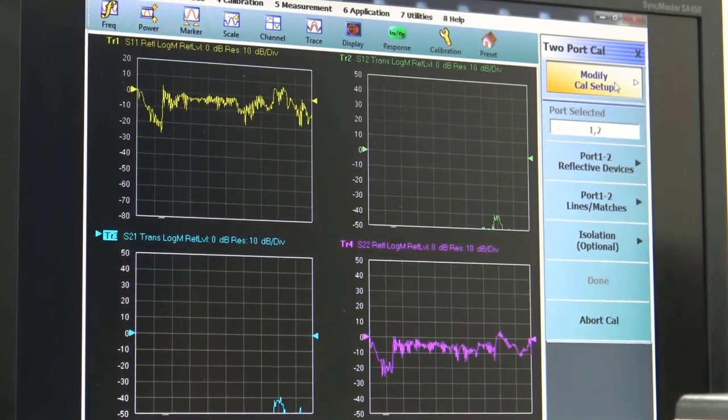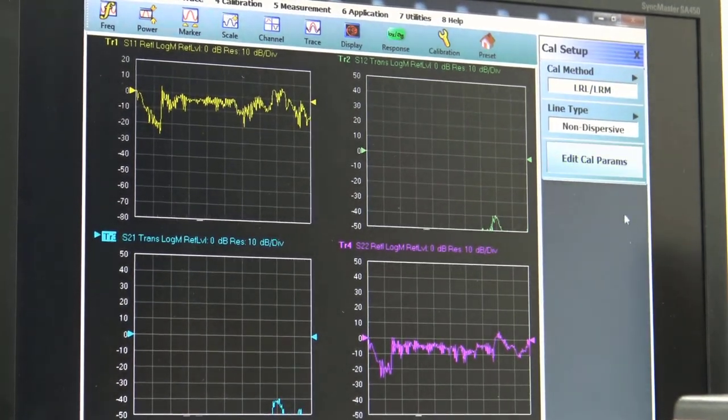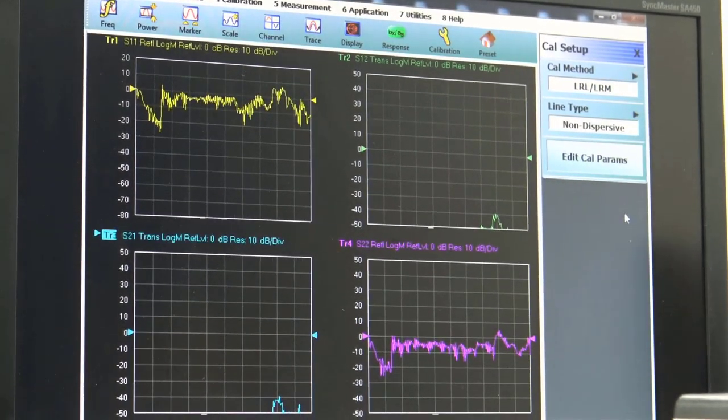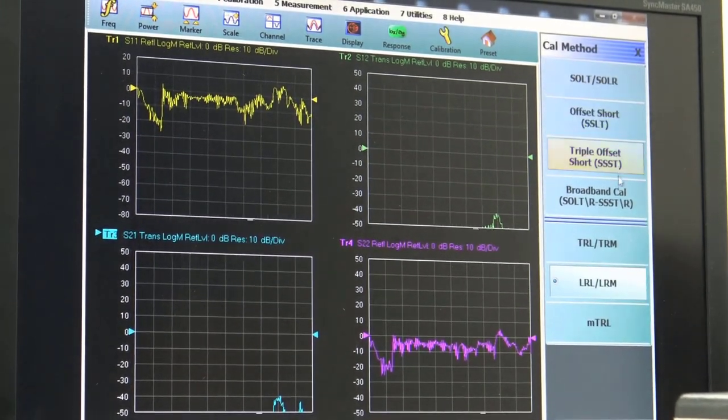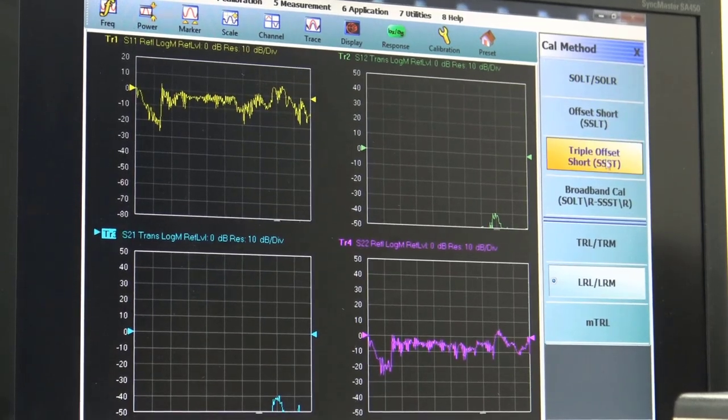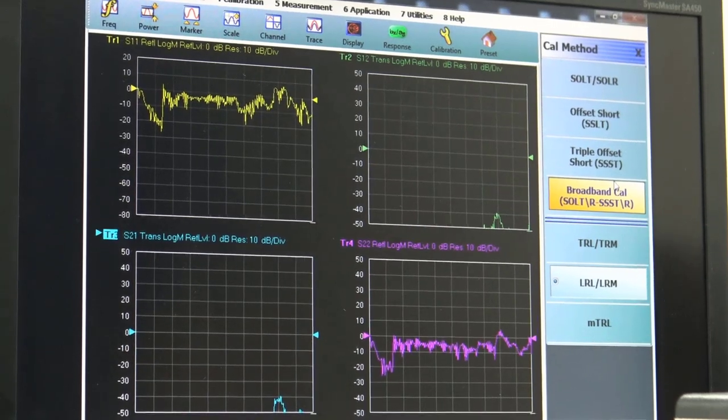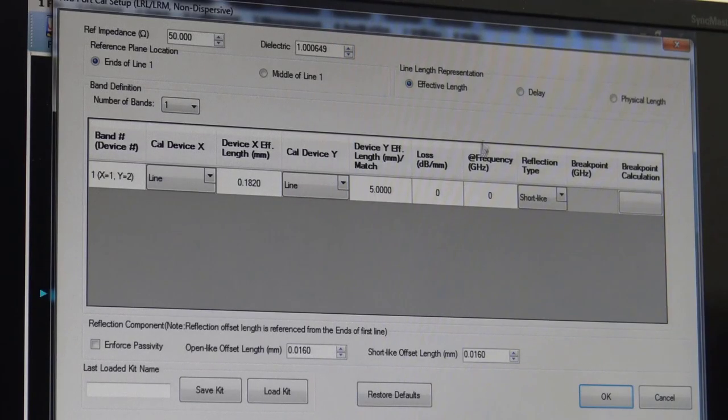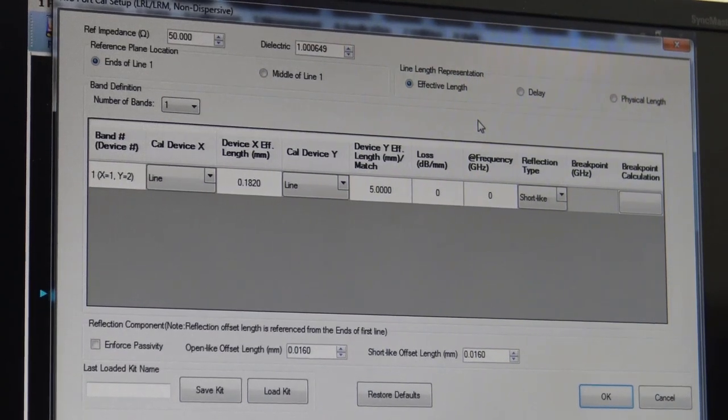We'll go first to modify cal-setup and this is where we define the type of calibration, the algorithm that we're going to be using. If we had a coax set up, then one of these would apply. They would also apply in other situations. So now that we know enough, if we have enough information on our calibration substrate, we can start to enter those parameters into our configuration panel here.